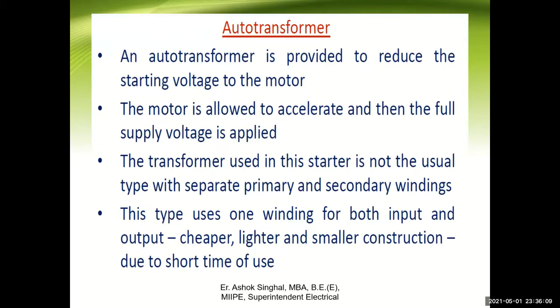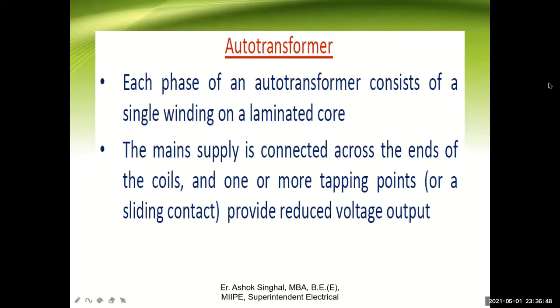An auto transformer is provided to reduce the starting voltage to the motor. The motor is allowed to accelerate and then the full supply voltage is applied. The transformer used in this starter is not the usual type with separate primary and secondary windings. This type uses one winding for both input and output, which is cheaper, lighter and smaller in construction due to the short time of use. Each phase of an auto transformer consists of a single winding on a laminated core. The main supply is connected across the end of the coil and one or more tapping points or a sliding contact provide reduced voltage output.